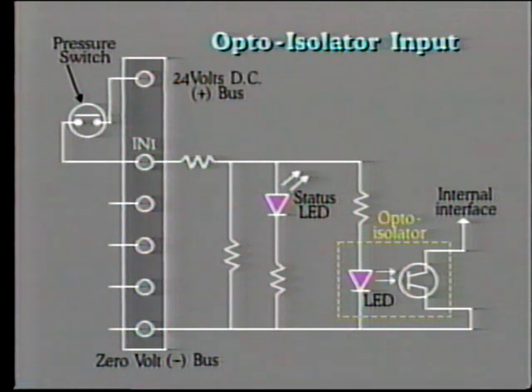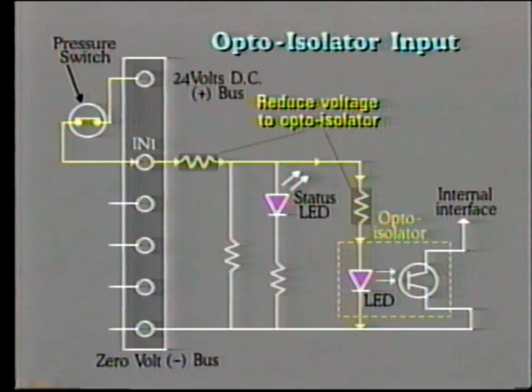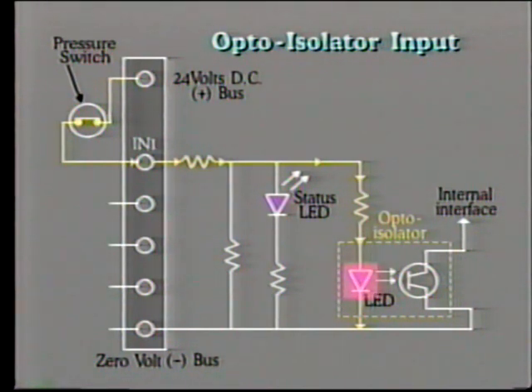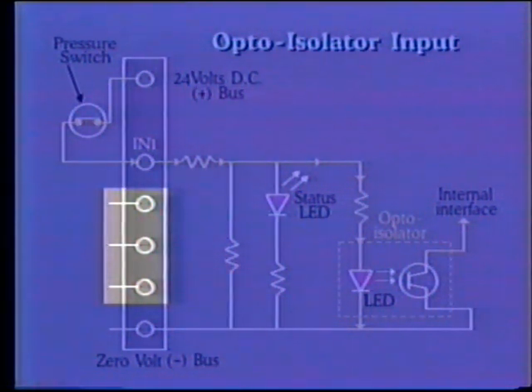One common method used in the interface to reduce voltage and provide the necessary isolation is to pass each incoming signal through an opto-isolator. This arrangement shows just one input terminal, and this particular sensing circuit uses 24 volts DC, which is supplied from the PLC. When the pressure switch closes at the sensor, the 24 volts is applied to the input terminal of the PLC. Current passes through several resistances as it returns to the zero voltage bus. The objective of the resistance is to reduce the voltage applied across the opto-isolator. When current passes through this LED, that is a light-emitting diode, the light triggers the phototransistor to provide a signal to the internal interface. The second LED provides indication when the signal is on. Each of the individual input terminals will need a circuit similar to this.